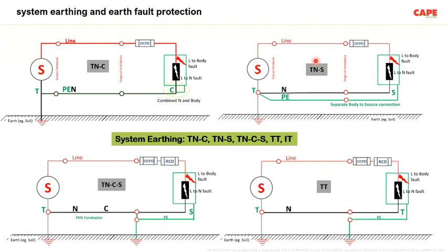In order to achieve safety, electrical systems, which is called system earthing, are classified into earthed systems and unearthed systems. In technical terms, they are called TN-C system, TN-S system, TN-C-S system, TT system, and there is one more, IT, which is used for special applications. IT is an unearthed system, which can be used for a specific location in order to achieve safety and continuity of the supply. Especially in the earthed systems, called TN or TT, supply must be disconnected to achieve safety. Whereas in case of an IT system, supply can continue during the first fault.